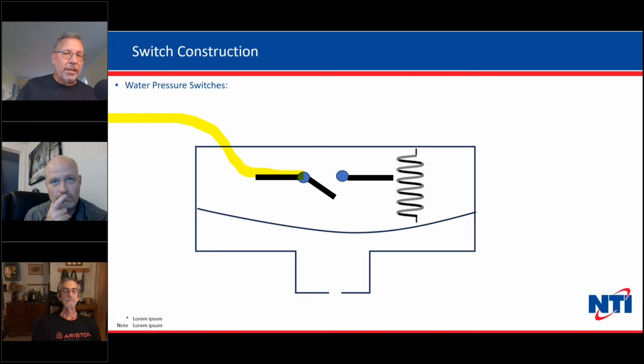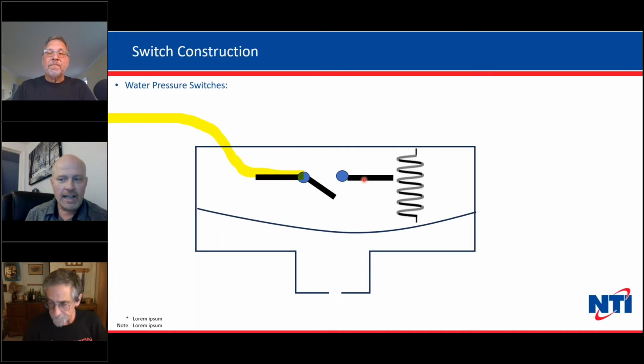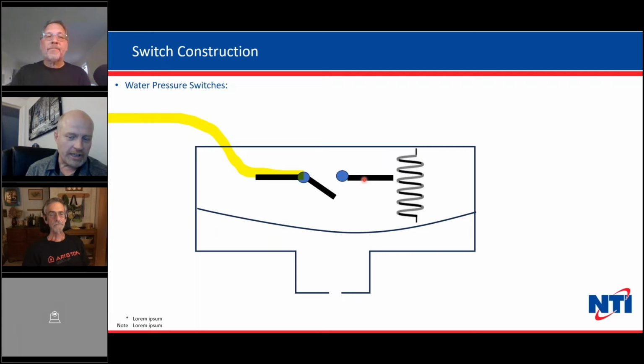Hey, Dave, can that be bypassed manually just by jumping out the two wires to see if it's the switch or not? Yes, anything that happens to be a switch, you can take your jumper wire, and again, I love jumper wires, and just connect the two blue dots together with your alligator clips. If it's a switch, you can jump it out. If you're not sure it's a switch, make sure you talk to somebody first, because there are certain sensors that if you jump them out by mistake, you'll actually fry the control board. Most of the time, it won't do any damage, but there are a few rare cases where jumping the wrong thing fries the board. So if it says switch in the instructions or in the parts breakdown, you're probably safe to jump it, I would say 99% of the time.